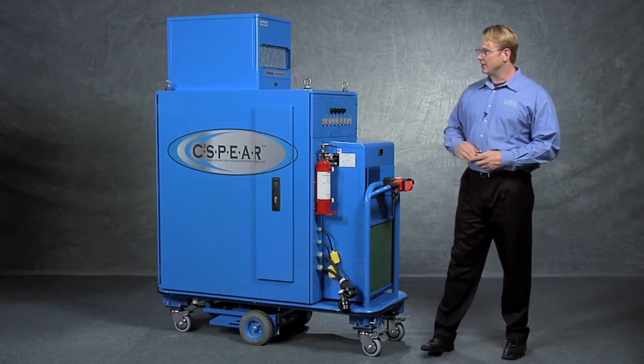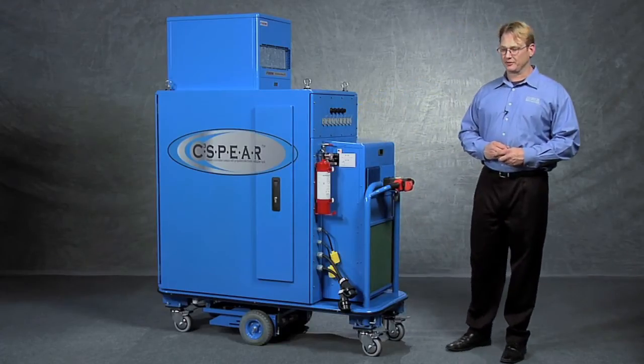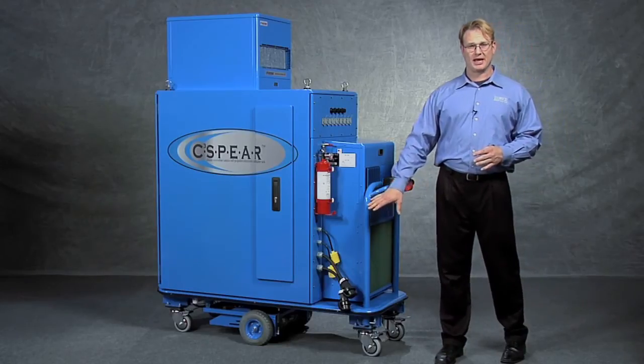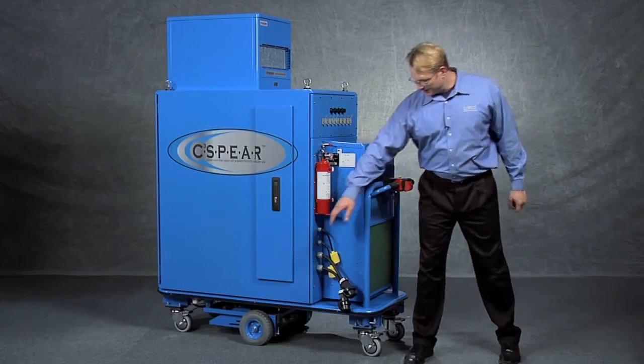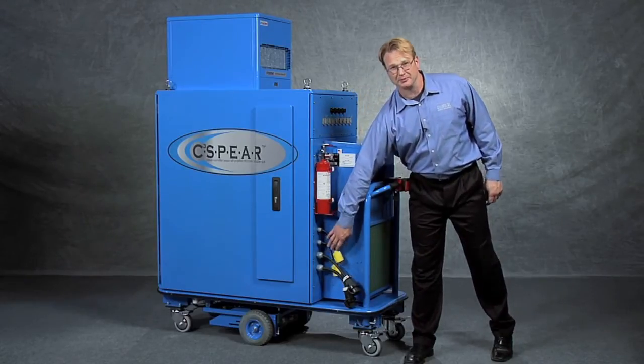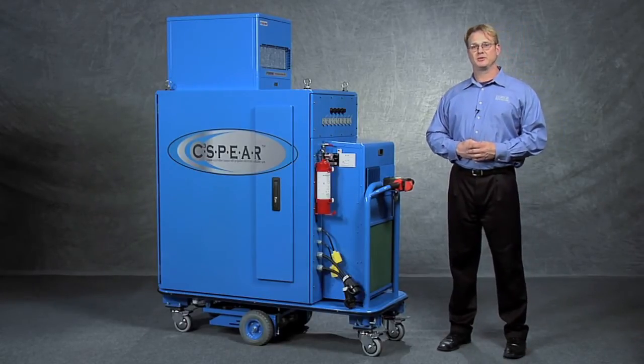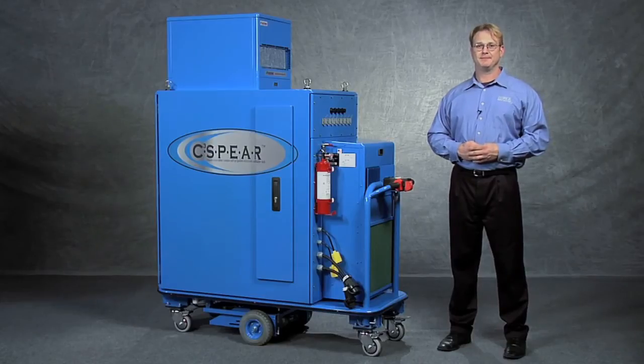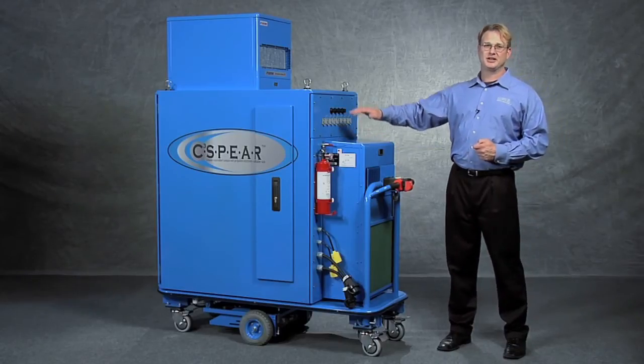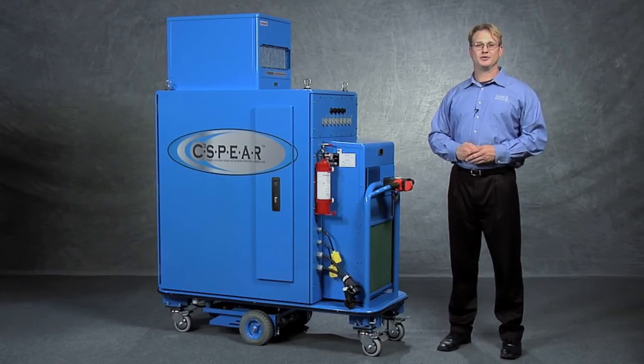We also include NEMA 4 doors, special hidden hinges, in addition to waterproof lock systems. The power system also has watertight connectors — watertight for the IT and for each air conditioner. This unit is currently equipped with a secondary AC that allows for complete redundancy or higher capacity. This unit can support between 2.5 kilowatts for just the rear air conditioner and an additional 3.5 kilowatts including the top AC, for a total of six kilowatts, or two and a half kilowatts fully redundant.